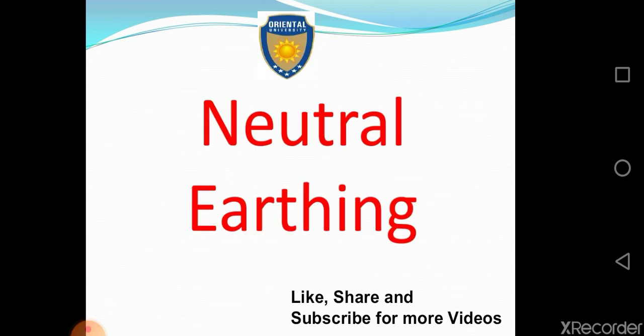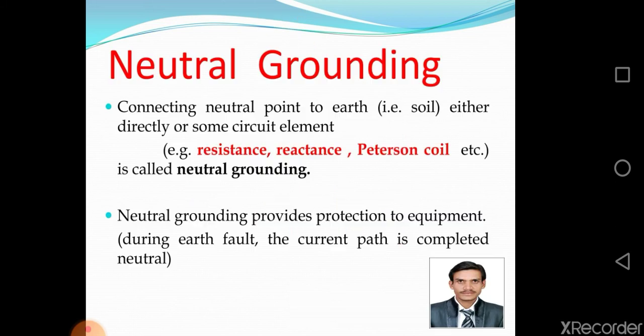Neutral earthing. Neutral grounding. Because the grounding and earthing is same, connecting neutral point to earth either directly or some circuit element like resistance, reactance, Peterson coil, etc. is called neutral grounding. Neutral grounding provides protection to equipment. During earth fault, the current path is completed through the neutral.